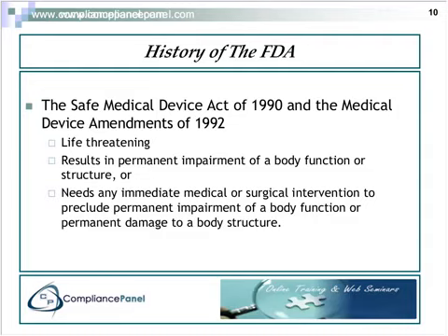The statute defines a serious illness or injury as life-threatening, resulting in a permanent impairment of a body function or structure, or needing immediate medical or surgical intervention. If this happened related to your device, prior to 1992, you weren't required to report this to the FDA. But that's when this part was implemented.